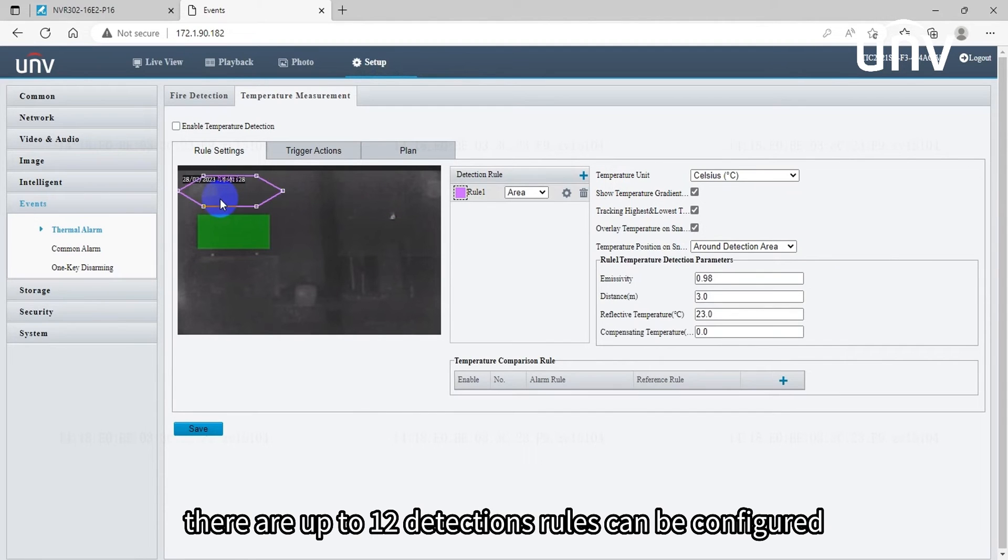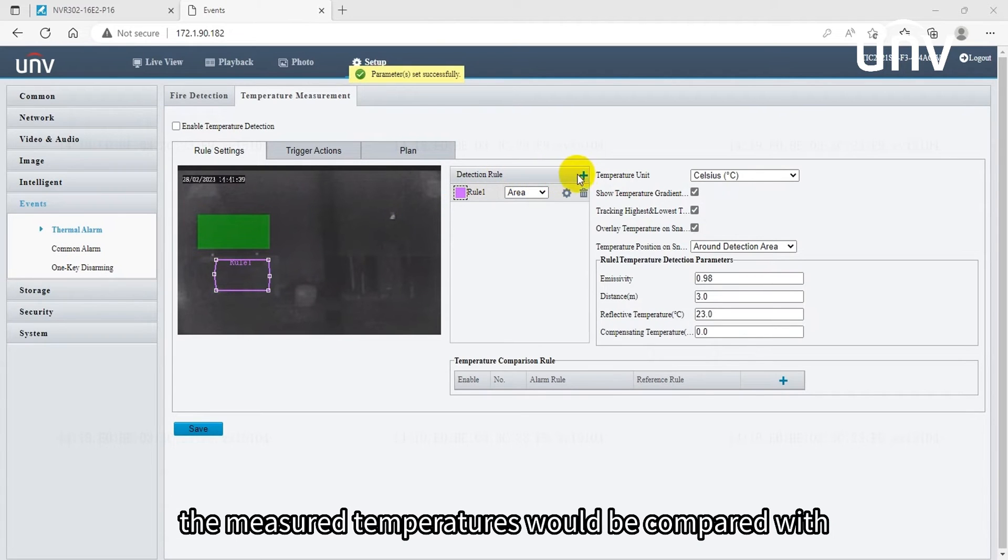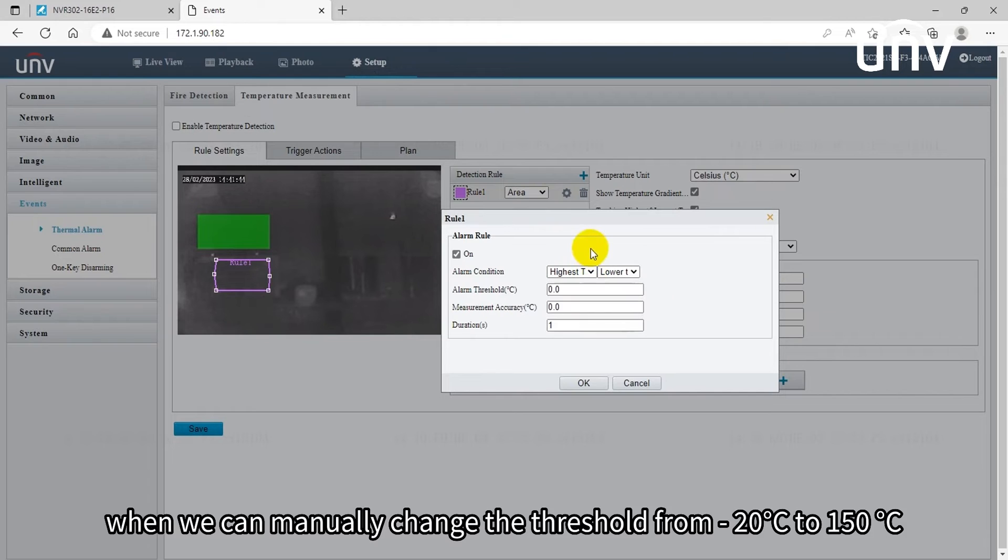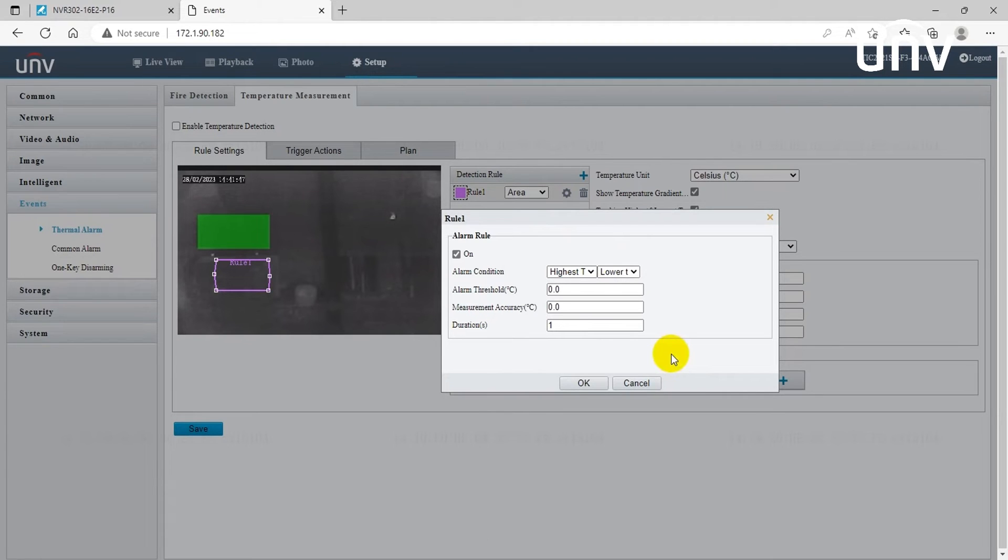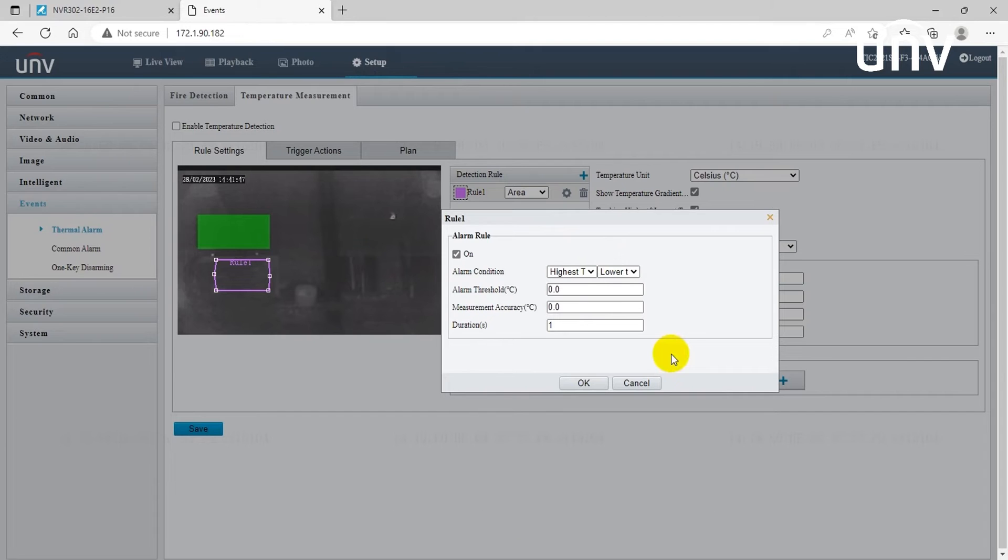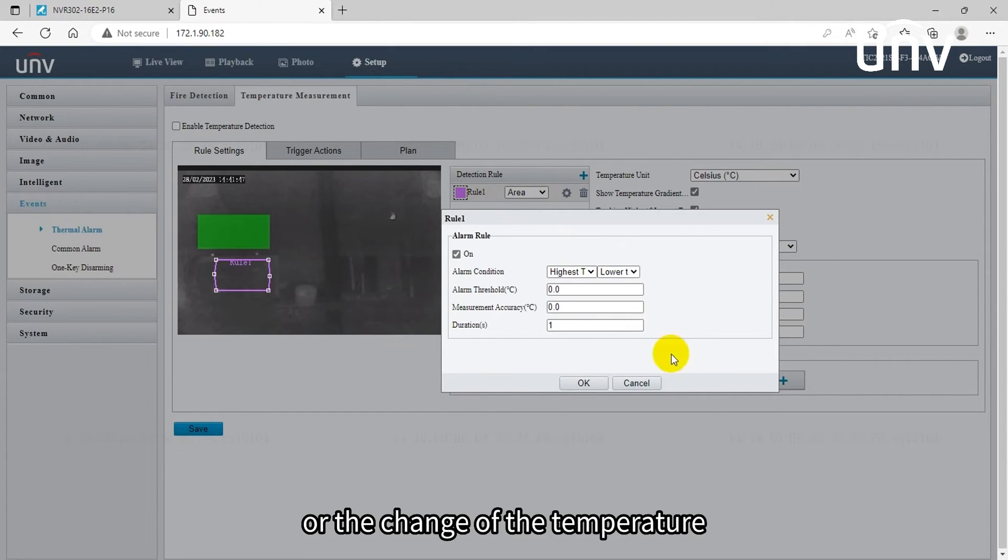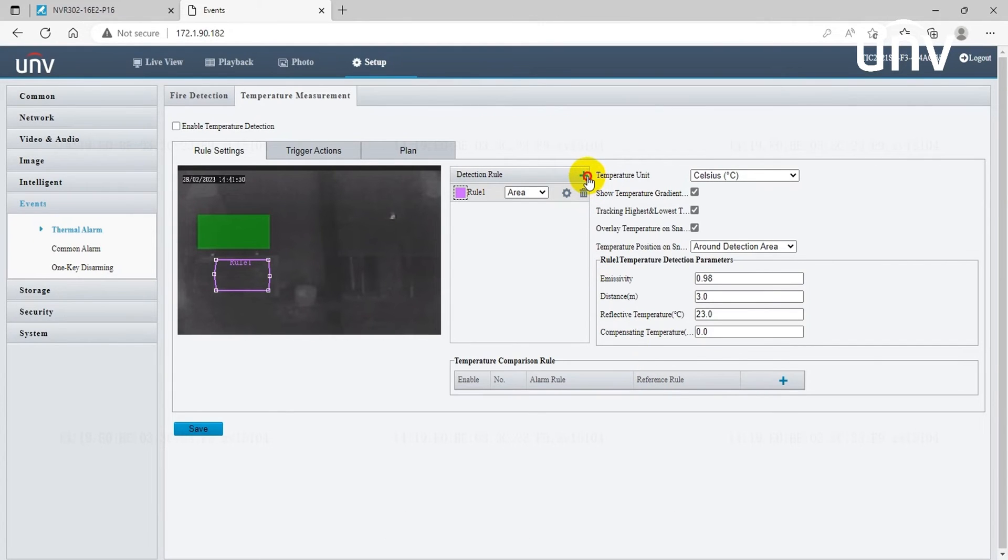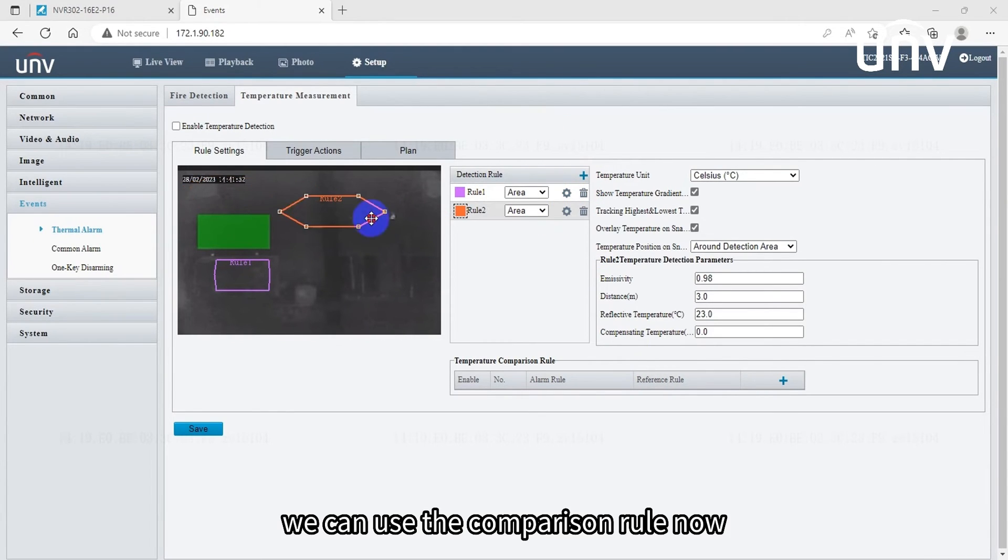There are up to 12 detection rules that can be configured. The measured temperatures would be compared with the set threshold value, and we can manually change the threshold from minus 20 degrees Celsius to 150 degrees Celsius. If there's a deviation we can use the measurement accuracy to calibrate. Duration here means the duration of the temperature or the change of the temperature.